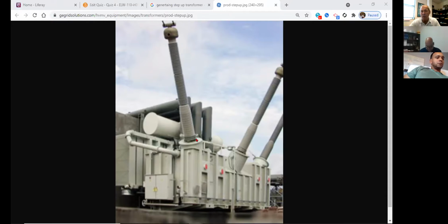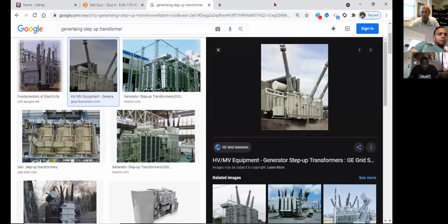You also notice on the transformer over to the side here, you see this big old pipe? Yeah. All right, and you see this tank that's on the top. These are radiator fins on the back with fans. So they're blowing fans through oil in these radiators, and this is actually pumping oil through the radiators. So they're also cooling the transformer itself. Cooler you keep it, the better it will conduct. You will actually get a lot more kVA out of this transformer if you just cool the oil in the transformer itself. Okay, let me see if I get one more picture here of something similar.